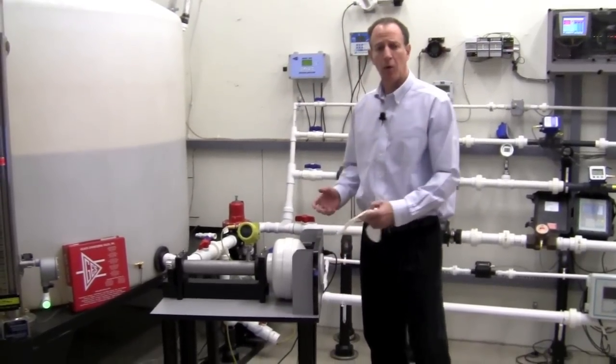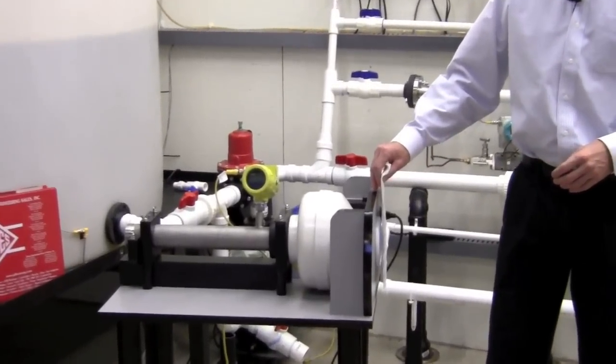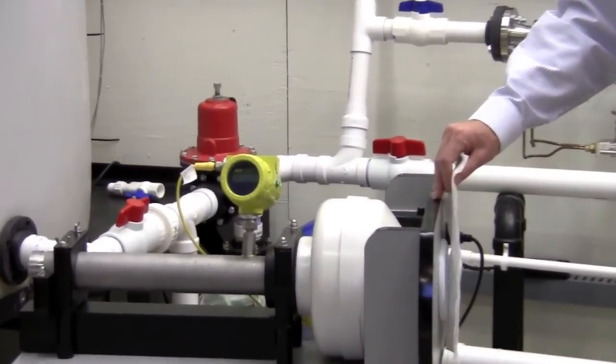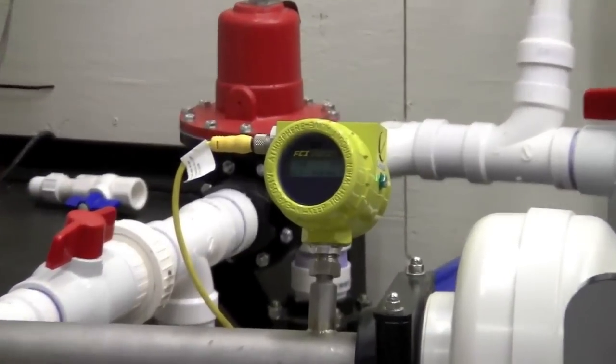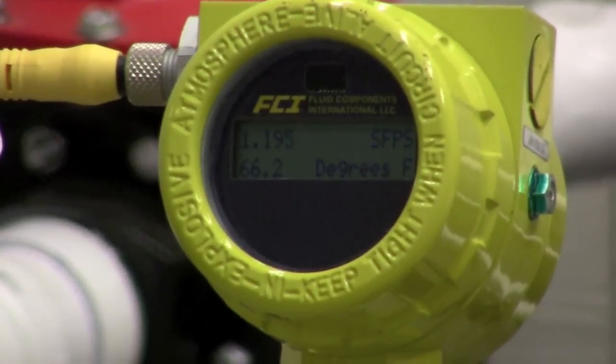With a blower on the lowest speed setting, barely enough to move this paper napkin, we're still registering flow. The ST series of flow meters will measure flow down to one foot per second.